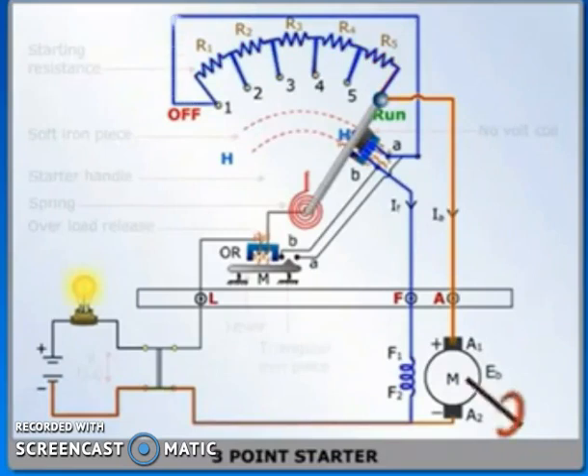Also, if the power comes on and the handle is not restored back to OFF position, current will pass through the handle and go to the armature without the starting resistance. Hence, the armature winding may get damaged as armature current is higher at starting.